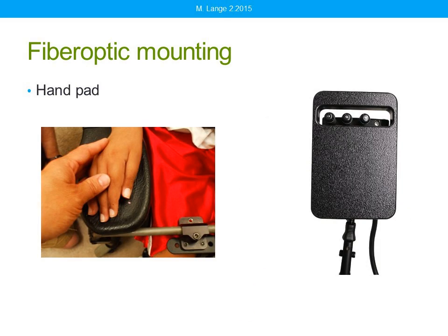For some clients with muscle weakness, if the client can flex their fingers over the edge of the tray, bringing the finger back into flexion might be an easier movement than moving them on a flat surface. Here with Julian, the fiber optic is mounted through the hand pad of an Ottobock arm trough — he has full support of his arm and hand. There's also a hand pad from Stealth Products with three fiber optic switches on short goosenecks so exact placement can be varied to match an individual client's needs.